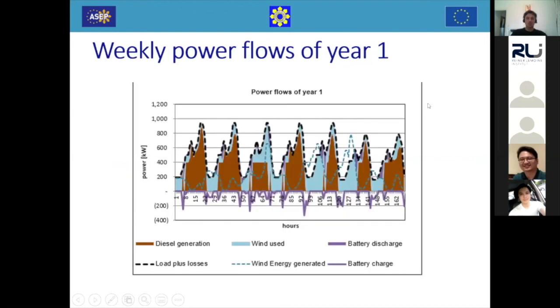Let's have a look at the weekly power flow. As we saw before, the wind speed is differently distributed, or stochastically distributed, throughout the weeks. So we have periods, for example here on the first day, we see that during the day there's just little wind speed, so the wind turbines can't generate a lot of power, and therefore the diesel generator has to jump on and cover the demand throughout the day as well as the peak load.